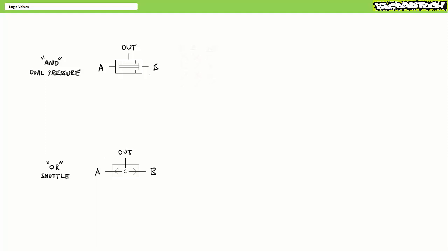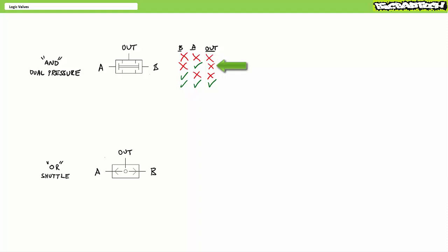Both valves have two inputs and one output. An AND or dual pressure valve works like this: there must be a pilot signal at both inputs A and B for there to be an output. A red X symbolizes the absence of an input or output, whereas a green check mark symbolizes the presence of an input or output. When neither A nor B receives an air pilot signal, the AND valve produces no output. When only A receives a signal, no output. When only B receives a signal, no output. Only when both A and B receive an air pilot signal does the AND valve produce output.